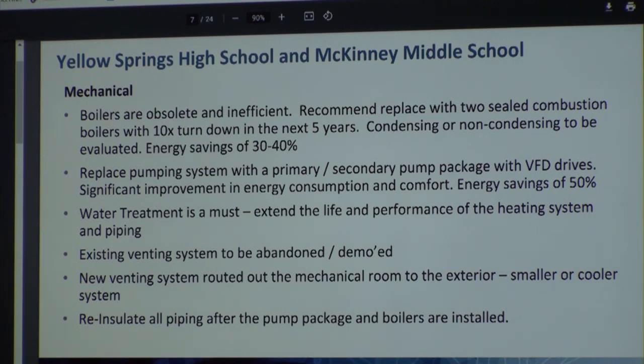They're pretty worn out. I would recommend a skid - they sell them as a skid package, primary and secondary pumps, all controlled by a VFD, and it probably saves you 50% of the energy in the pumps.